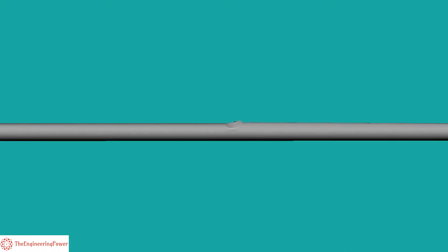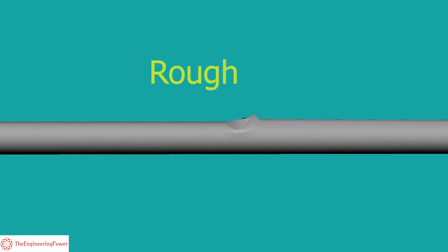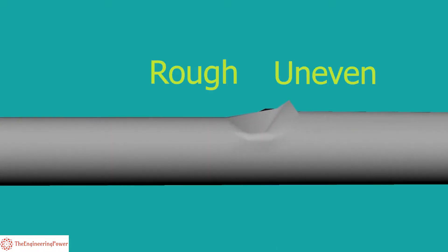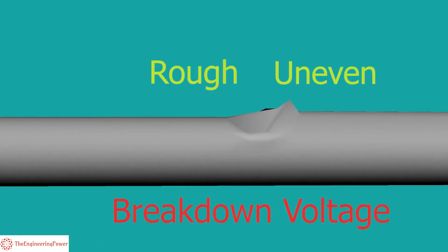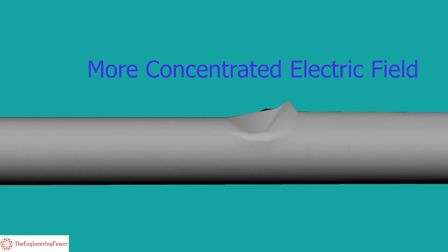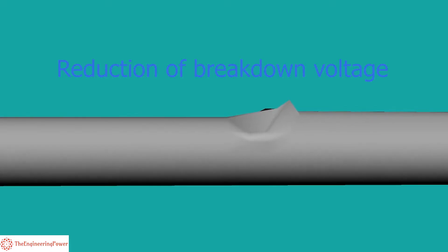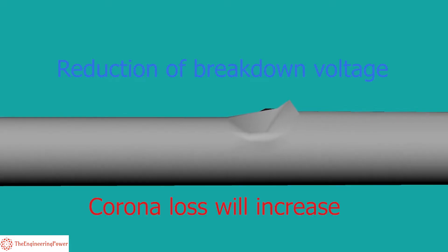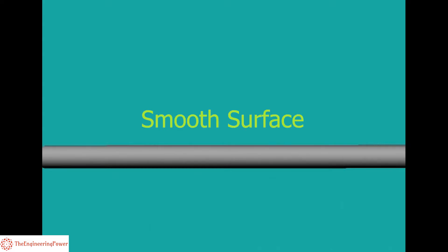If the surface of the conductor is rough and uneven, it will decrease the value of the breakdown voltage, as the electric field will be more concentrated at rough spots. With the reduction of breakdown voltage, the corona loss will increase. On the other hand, corona loss will be less in conductors having a smooth surface and hence a uniform electric field.